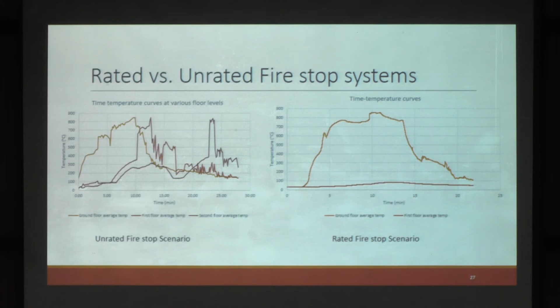Now the red curve, this one, that is the temperature of the first floor. So in this case where the compartmentation is not proper, what we see is that at around 10-minute mark, the first floor temperatures rise very abruptly. Okay? And basically what that means is if we are in the first floor, then after 10 minutes there is very, very little hope of escape. Whereas in this case where there is a proper compartmentation, the first floor temperatures throughout the test would remain below 100 degrees. Although 100 degrees is also not tenable, but there is at least a greater chance of escape or less damage to the property of the first floor in case this type of thing is used.